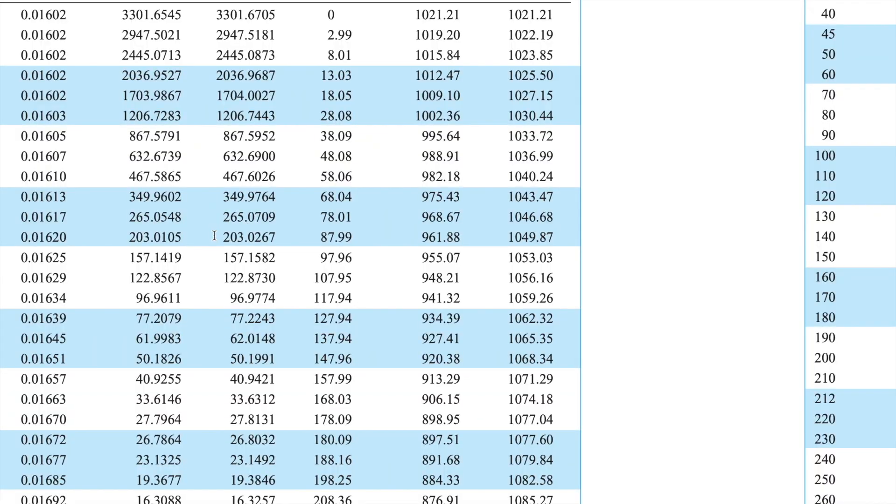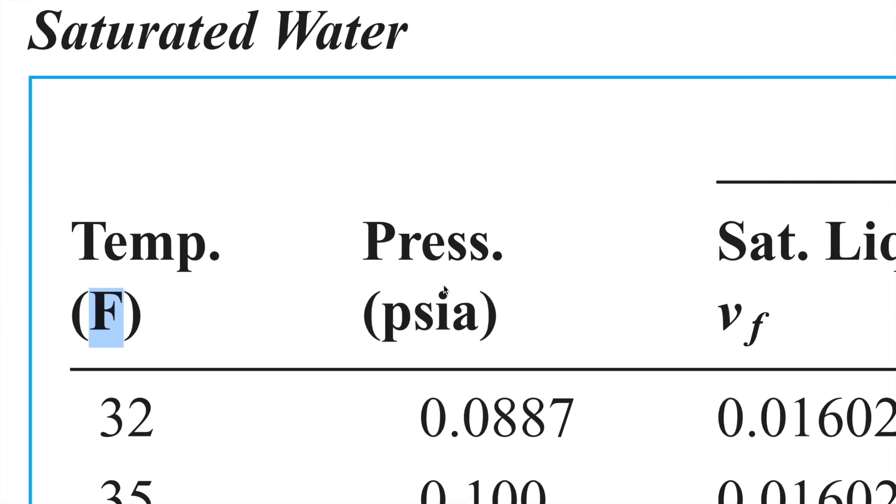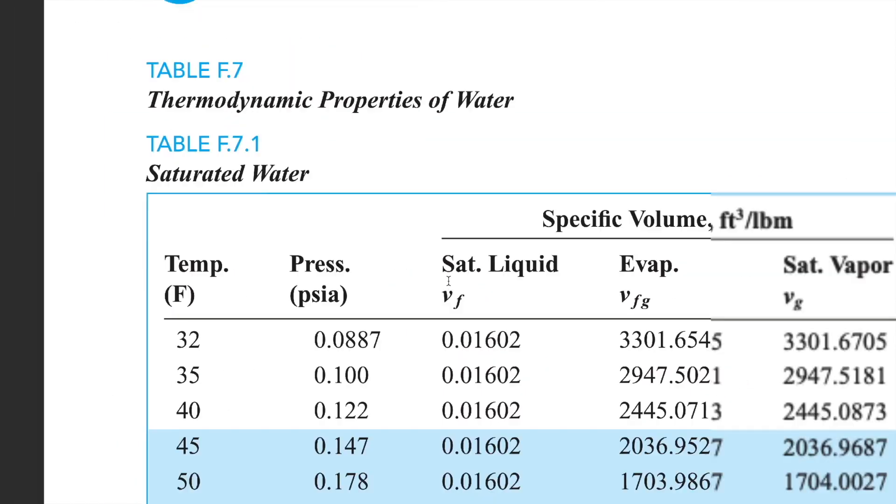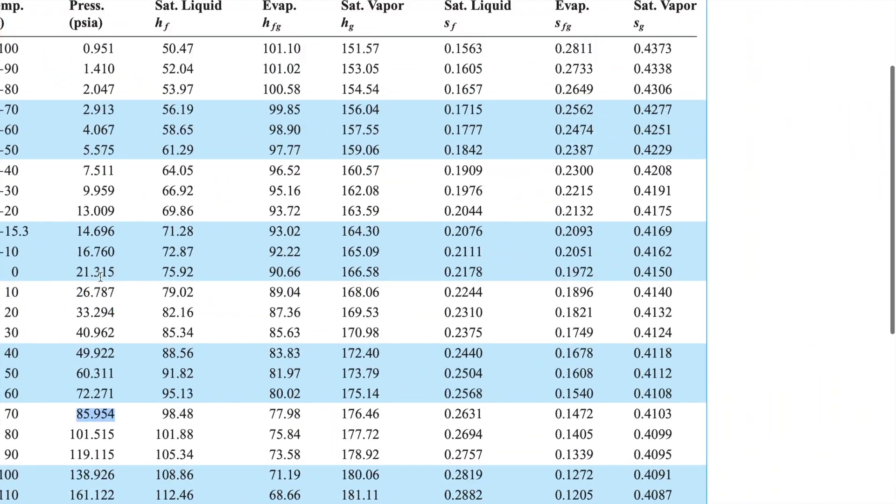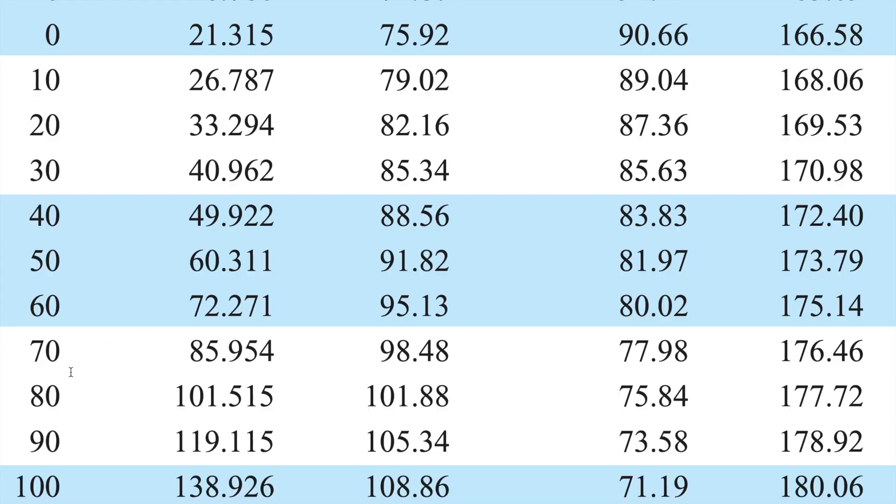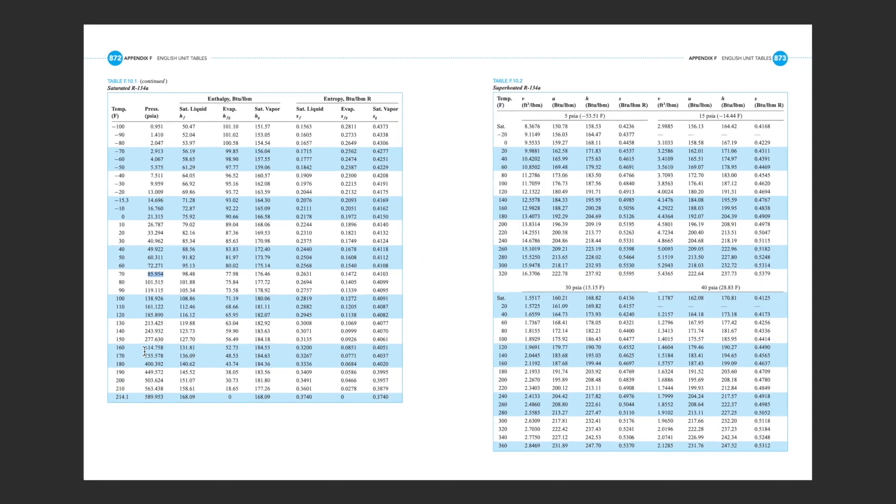Here we are in the English unit tables where we have the more familiar to my American friends Fahrenheit and psi. PSI A just means actual pressure, not gauge pressure, which basically means atmospheric pressure in PSI A is 14.7. Atmospheric pressure in PSI G is zero. So basically relating to the ambient, PSI G means gauge pressure, PSI A is actual pressure. So here we are in the R134A English unit tables. If we go to 70 degrees Fahrenheit, we get to 85 PSI A. So 70 gives us 85. And that's probably because 70 degrees Fahrenheit is a little bit less than 25. 70 degrees Fahrenheit is the temperature it is in my house right now. So 85 PSI is what we will get, might be a little warmer than 70. So maybe 90 will come out during this test, but we will find out.